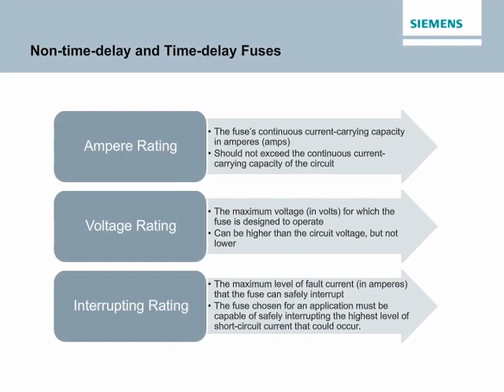Fuses are also rated according to the level of fault current they can interrupt. This is referred to as the interrupting rating of the fuse and is expressed in amperes, often shortened to amps. A fuse for a specific application should be selected so that it can sustain the largest potential short circuit current that could occur in the application. This is important because if the fault current exceeded the interrupting ability, the fuse could rupture and extensive damage could occur.